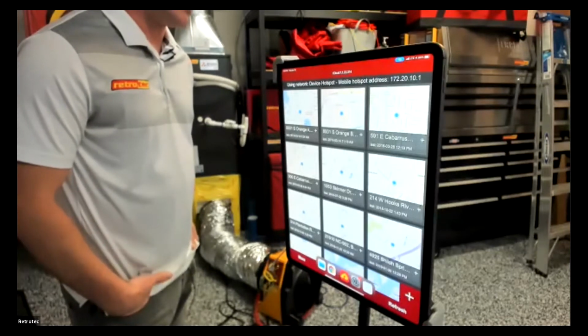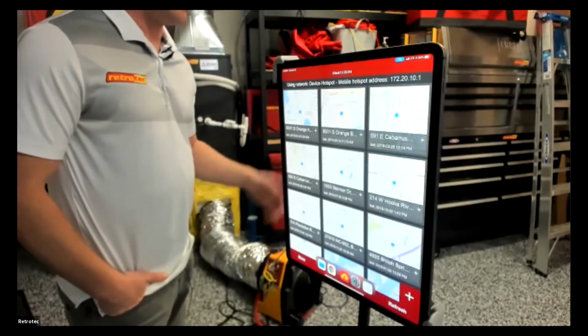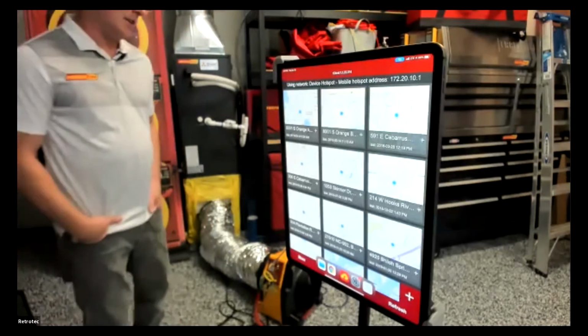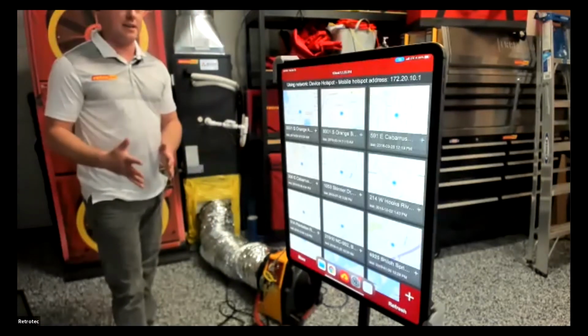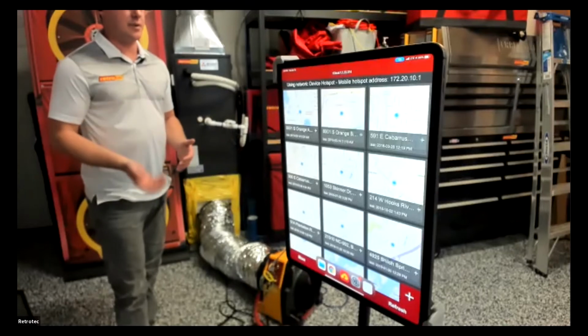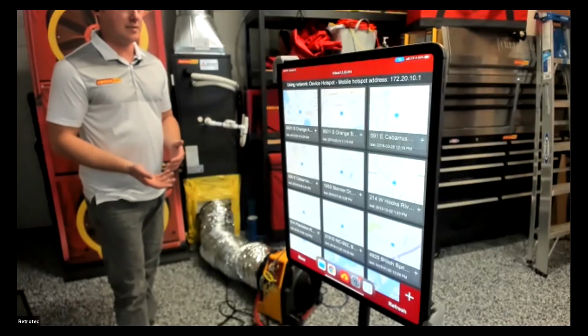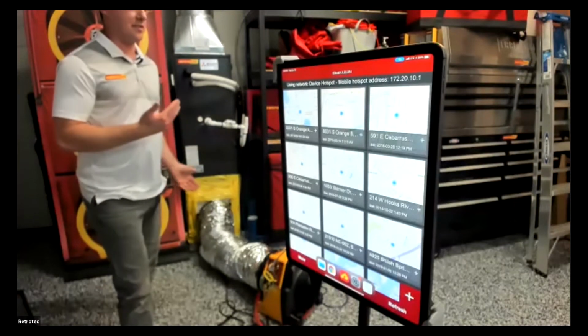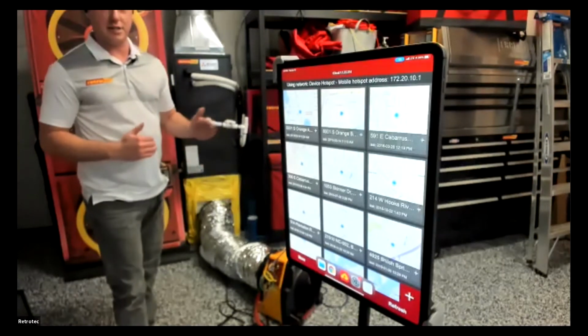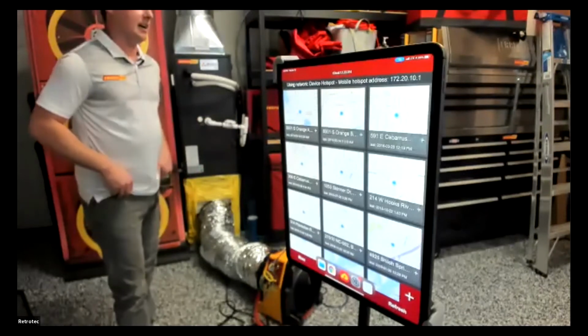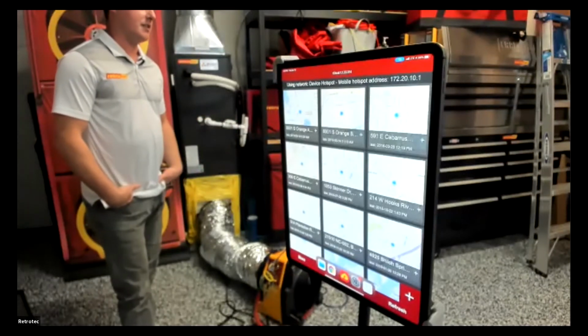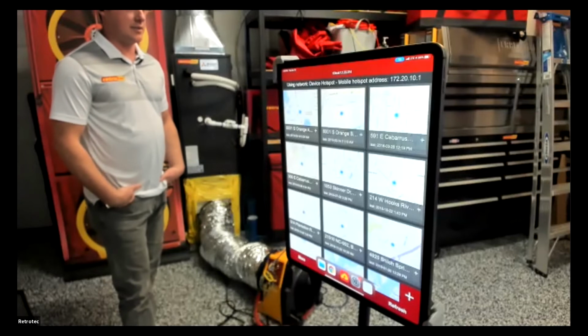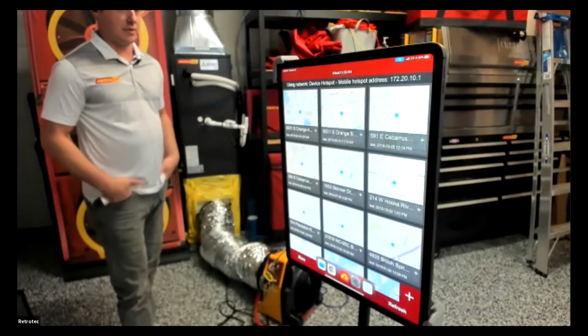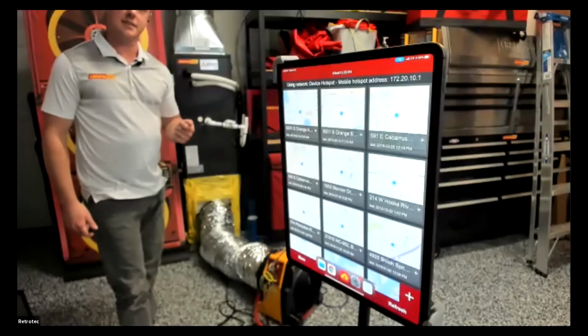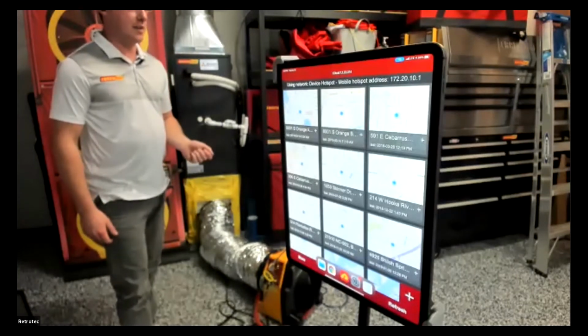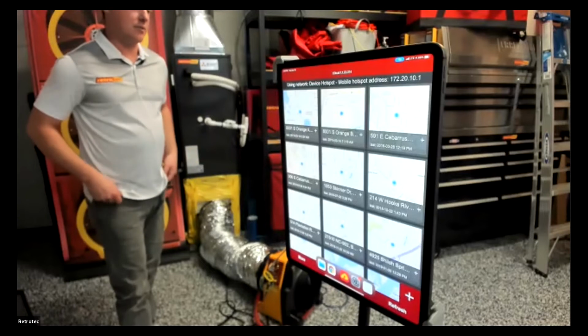What we're going to do here in the next few minutes is do it to where you have your blower door that's independent from the duct tester, depressurizing the house to negative 25 pascals, and then you just have the duct tester seek zero to neutralize the pressure between the duct system and the house, and that gives you your duct leakage to the outside. Or what you can do is tether those two manometers together with a tubing T connector to reference to the outside, and then you can have both pieces of equipment seek 25 pascals.